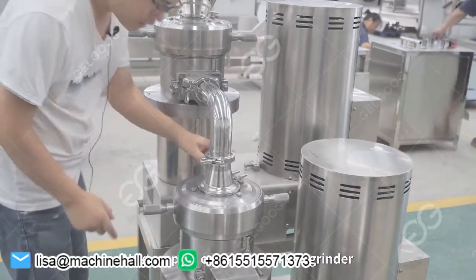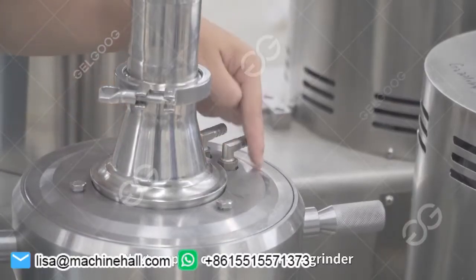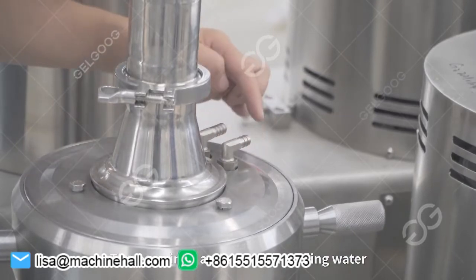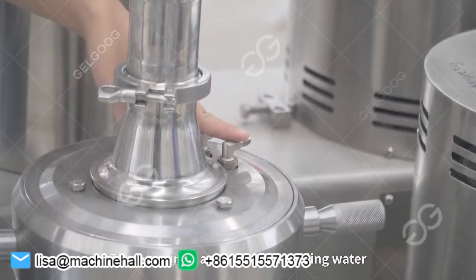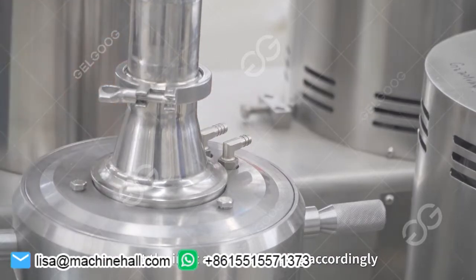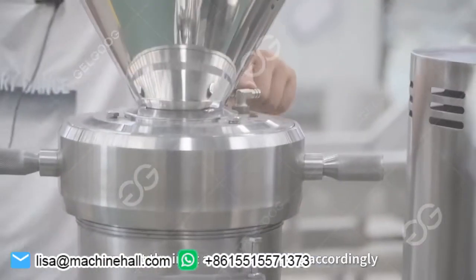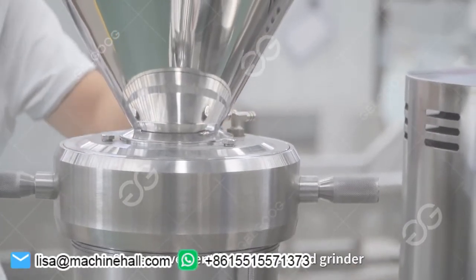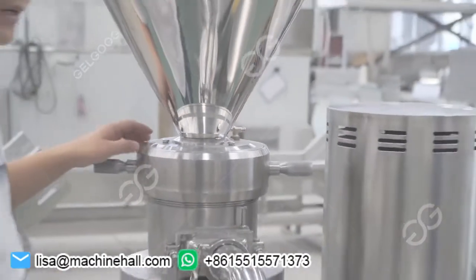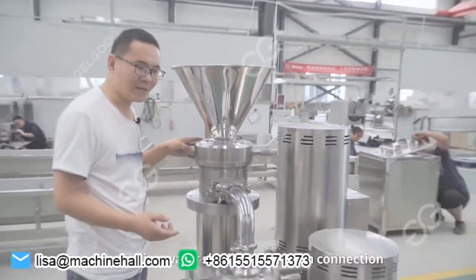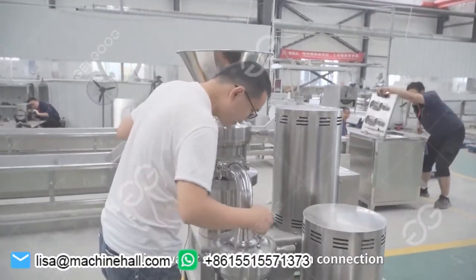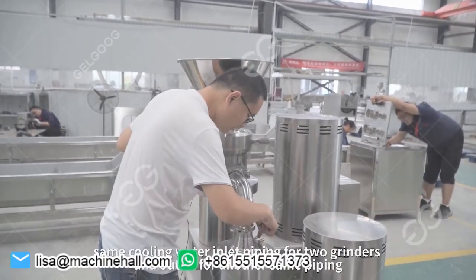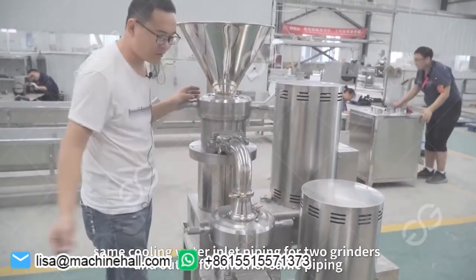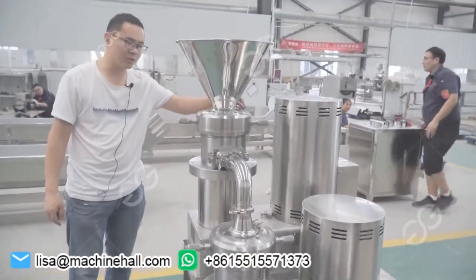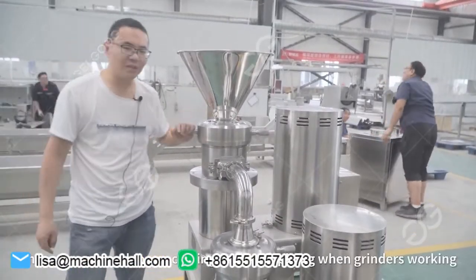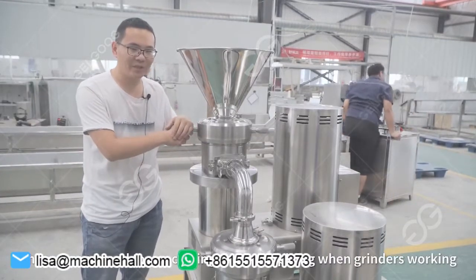Next, supply cool water for the grinder. There are an inlet and an outlet for cooling water. Connect the inlet and outlet piping accordingly. Do the same for the overhead grinder. The cooling water shall be connected in parallel. Use the same cooling water inlet piping for the 2 grinders, and the same piping for the outlet. It is recommended to supply cooling water when the grinders are working.